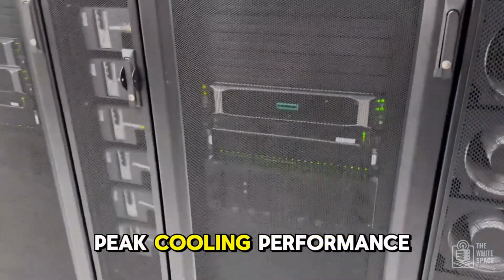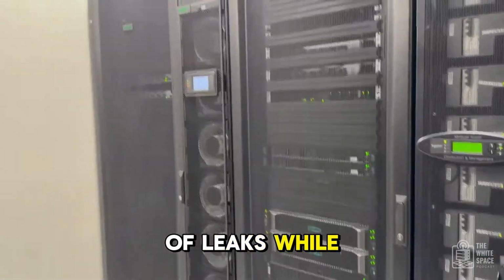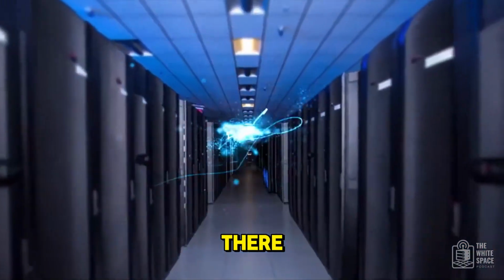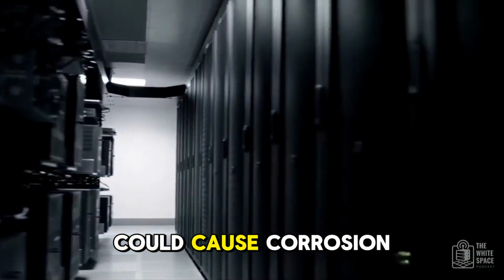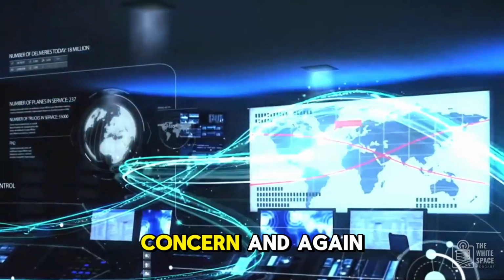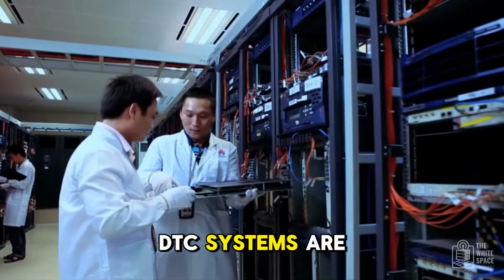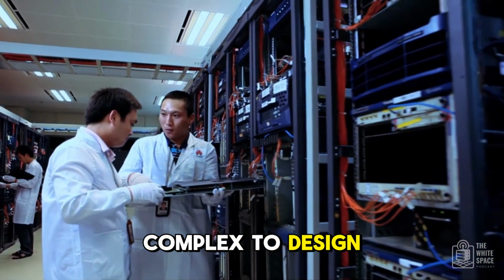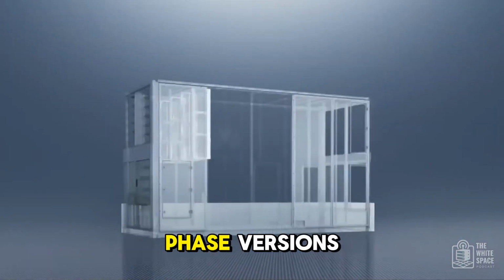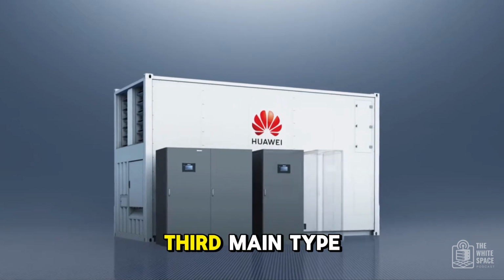And the cons for DTC? Well, the absolute peak cooling performance isn't quite as high as you can get with full immersion, and the risk of leaks, while managed, is always there. A leak directly onto a motherboard could cause corrosion or short circuits. That's a major concern. And again, the two-phase DTC systems are generally seen as more complex to design, manage, and maintain than the single-phase versions. Got it. Okay, let's cover the third main type.